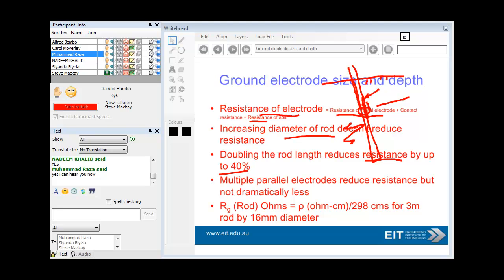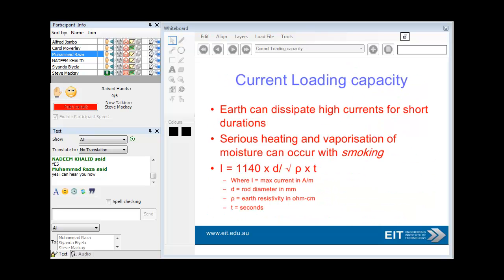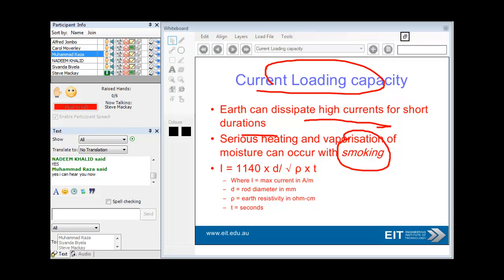The other way to reduce resistance is to put in multiple parallel electrodes - here's a typical example. Resistivity is measured in ohm centimeters or ohm meters, though ohm centimeters is often used. You calculate resistance with rho in ohm centimeters divided by 298, for a 3-meter rod by 16-millimeter diameter - quite a thick rod. That just gives you a quick example. Another thing to consider is current loading capacity: earth can dissipate high currents for short durations, but you've got to watch out for smoking if there's a lot of current going through the earth rod. This is the calculation here for the maximum current in amps per meter.